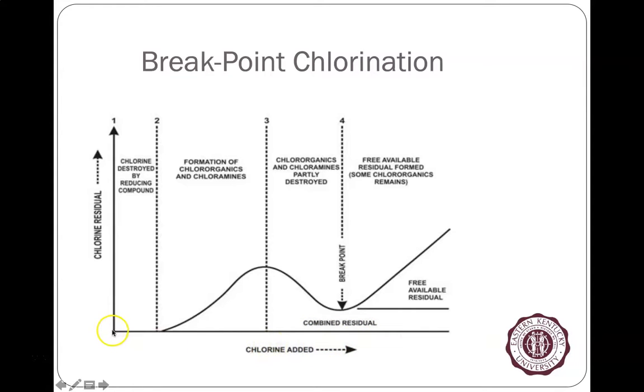If you have crystal clear water with nothing in it, as soon as you add chlorine, you might just immediately go up without having a breakpoint at all. But we don't have crystal clear water. Natural water has stuff in it. Even after coagulation, flocculation, sedimentation, and filtration, we've still got water that has stuff in it that will react with the chlorine.